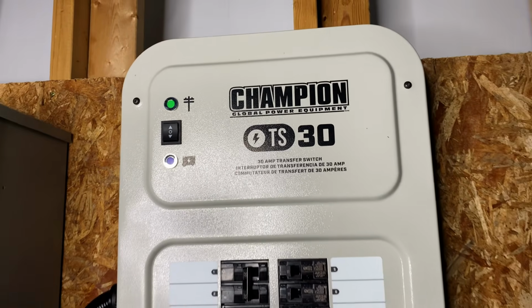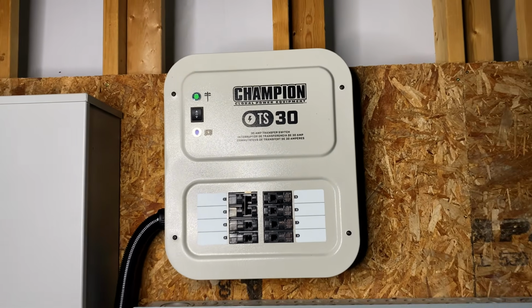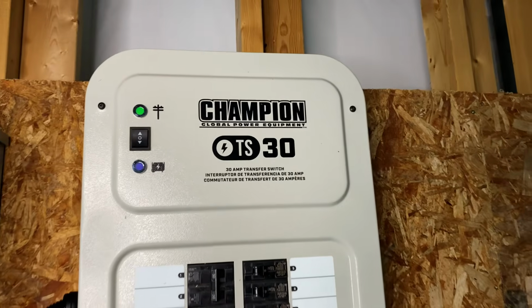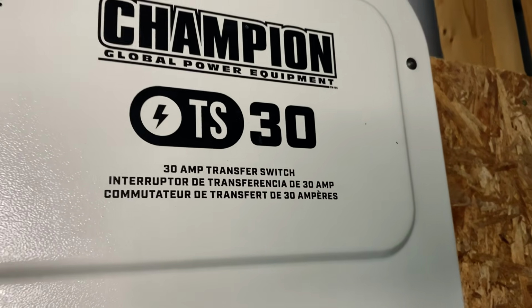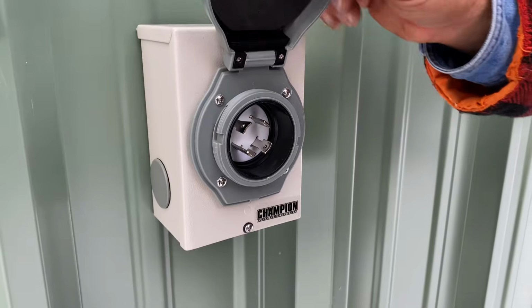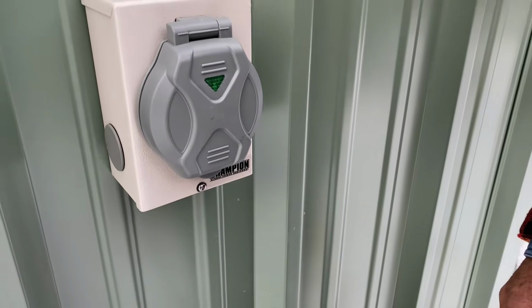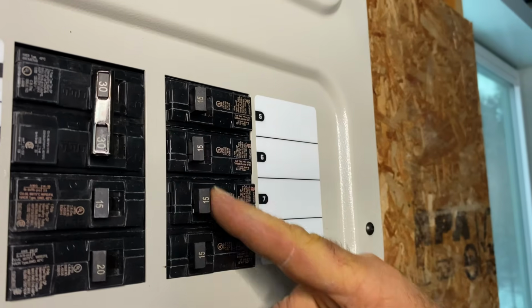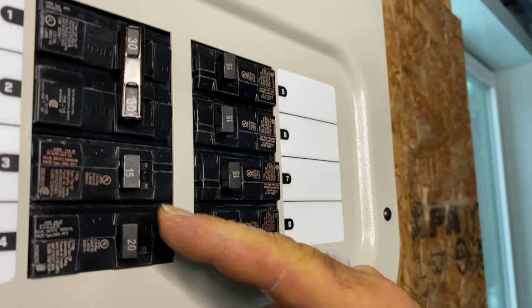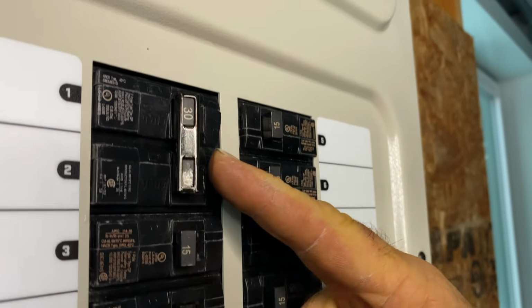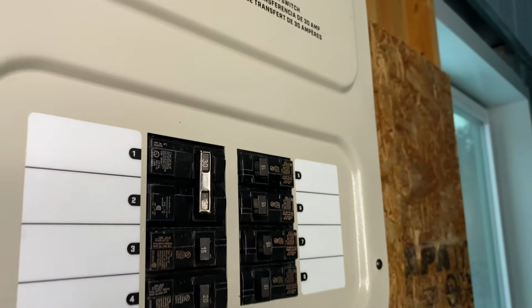and buildings. The Champion TS30 unit that I have at my place cost $599 Canadian, or about $499 US. And this is about as economical as it gets for this kind of thing. My model handles 30 amps at 240 volts, which translates to 7,200 watts of total power delivered, large enough to handle the output of most generators for household backup. The unit comes with a weatherproof outlet, a power cord to connect a generator to the port, 5 120 volt 15 amp protected circuits, one 120 volt 20 amp protected circuit, and one 120/240 volt 30 amp protected circuit.